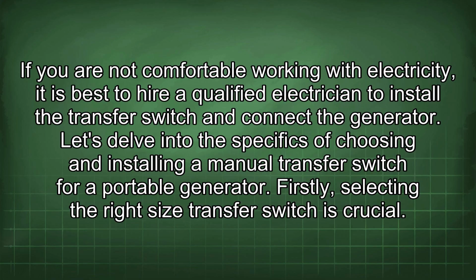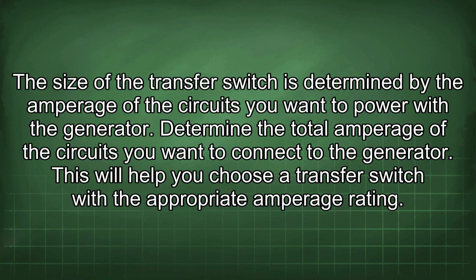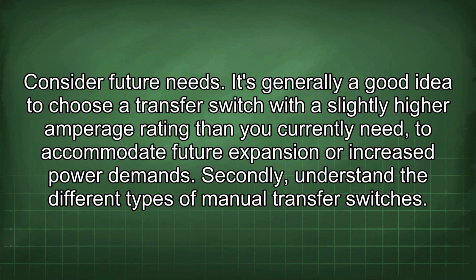Firstly, selecting the right size transfer switch is crucial. The size of the transfer switch is determined by the amperage of the circuits you want to power with the generator. Determine the total amperage of the circuits you want to connect to the generator. This will help you choose a transfer switch with the appropriate amperage rating. Consider future needs. It's generally a good idea to choose a transfer switch with a slightly higher amperage rating than you currently need to accommodate future expansion or increased power demands.